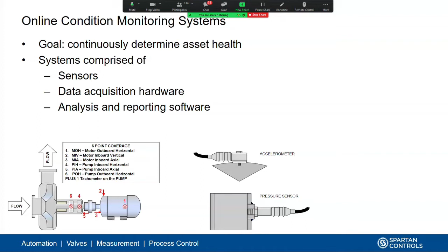So we'll put those sensors at different locations on the pump and the motor, and then wire those sensors back into a data acquisition hardware platform. Typically a rack-mounted system with a control processor and I/O processors, contained in a cabinet out in the field. The wires from the sensors connect to terminal blocks on this data acquisition system, which sits out in the process area.